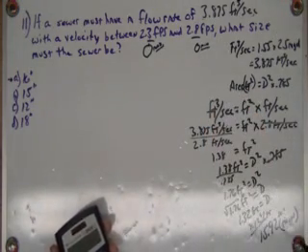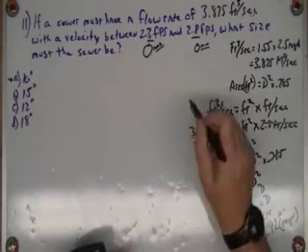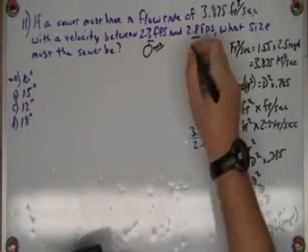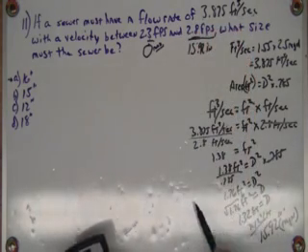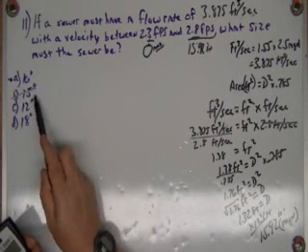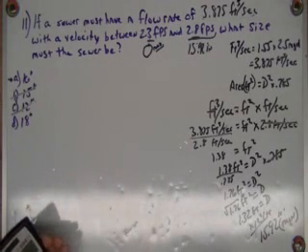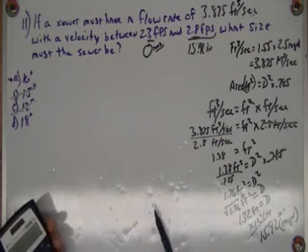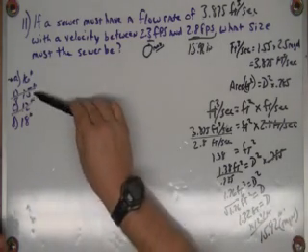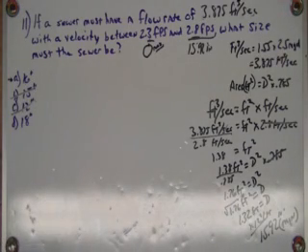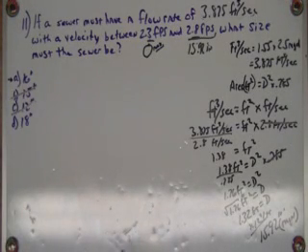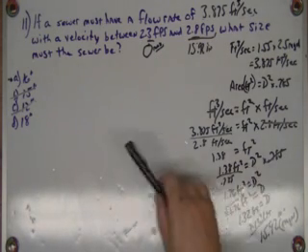So the minimum pipe size is 15.92 inches. That means 15 inches won't work — it's under 15.92. The answer is somewhere between 15 and 16 inches. However, there's a remote chance the slower velocity of 2.3 ft/s could give a maximum pipe size under 16 inches, so to be safe we'll do the second half of the problem.